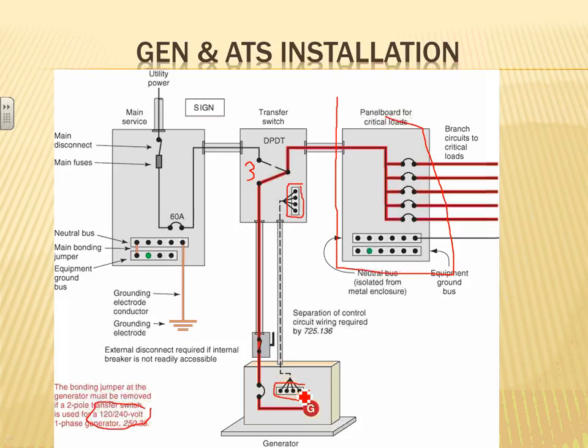My understanding is, if you have a separately derived system, it will give you a four pole. If it's a non-separately derived system, you get yourself three poles, so cheaper equipment. But what do you guys prefer? Do you prefer running separately or non-separately? I know in bigger systems, when we have paralleling switchgear, you run a non-separately derived system, you tie the neutral all together so you can parallel the switchgears. But in smaller systems, where you're transferring with an auto transfer switch, you really have the option. Yeah. Three pole. Yeah, you tie the neutral together.